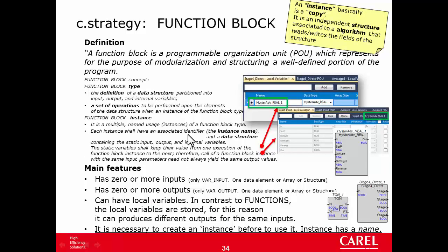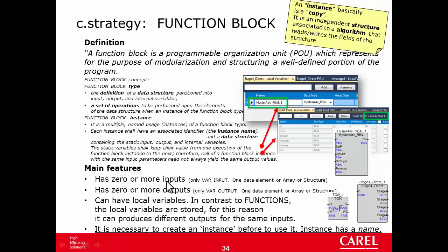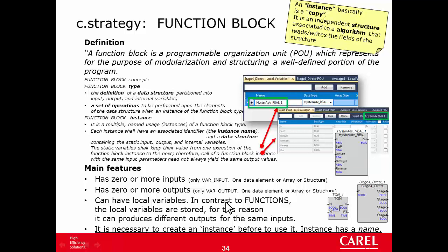The other type of block is the function block. This is the definition by the standard. The main features. A function block has zero or more input, like the other block. A function block has zero or more output. This is different compared to the other block, because the other can have just one. A function block can have local variable, but in contrast to the function, the local variable are stored.